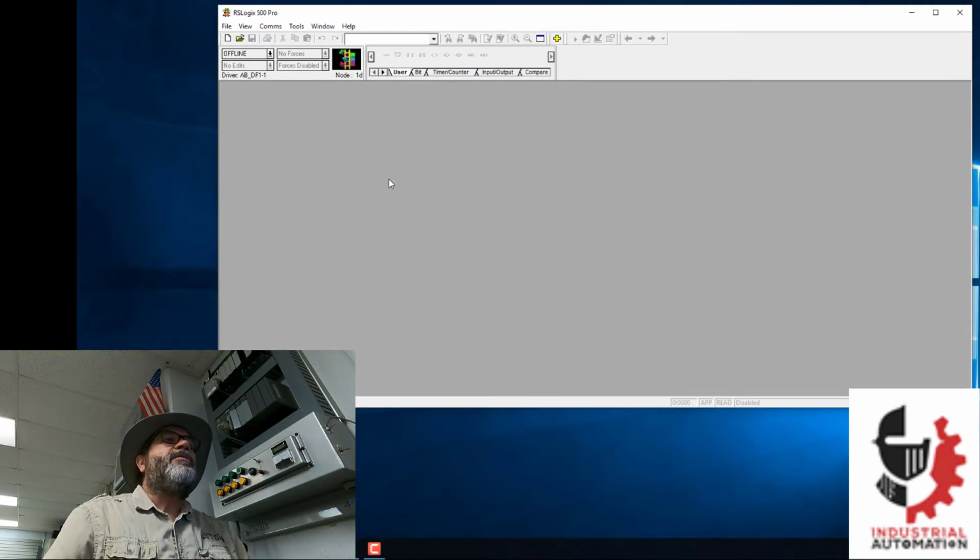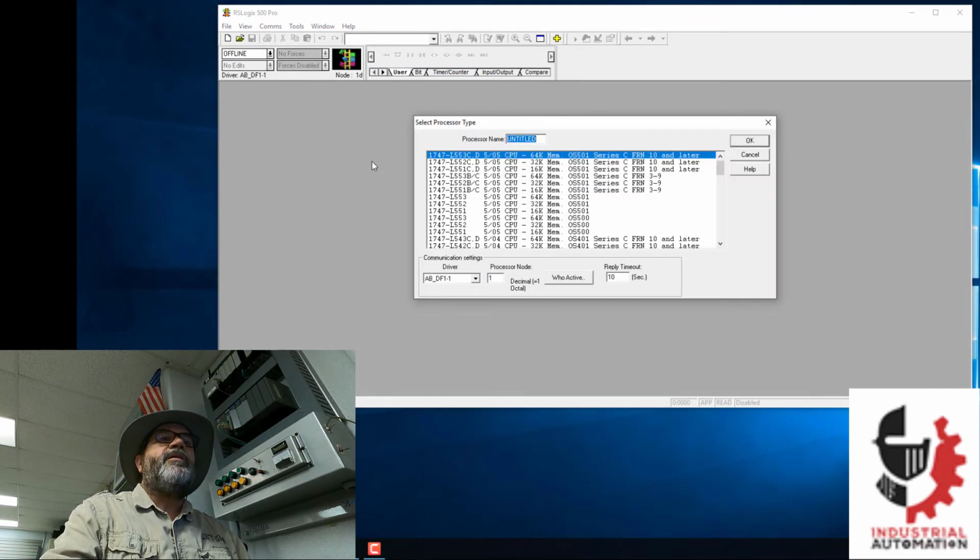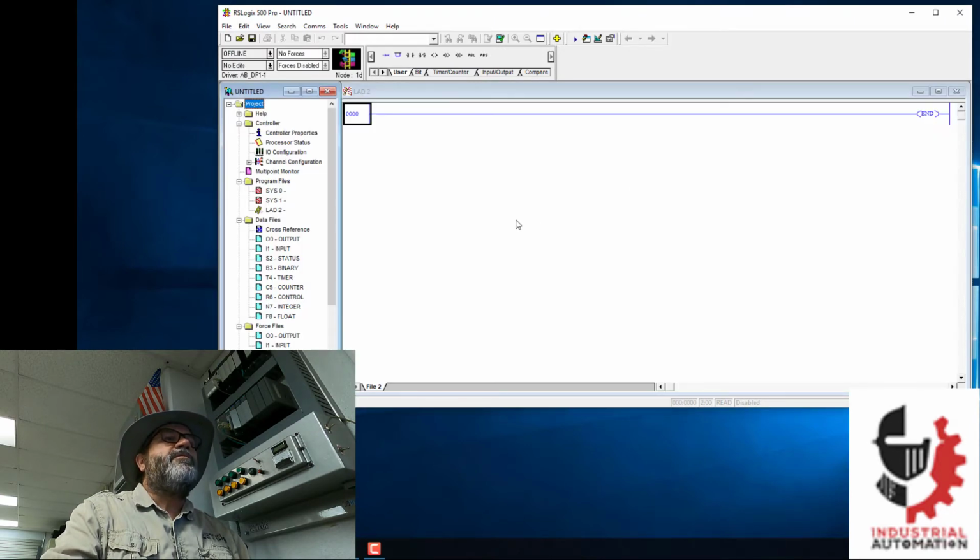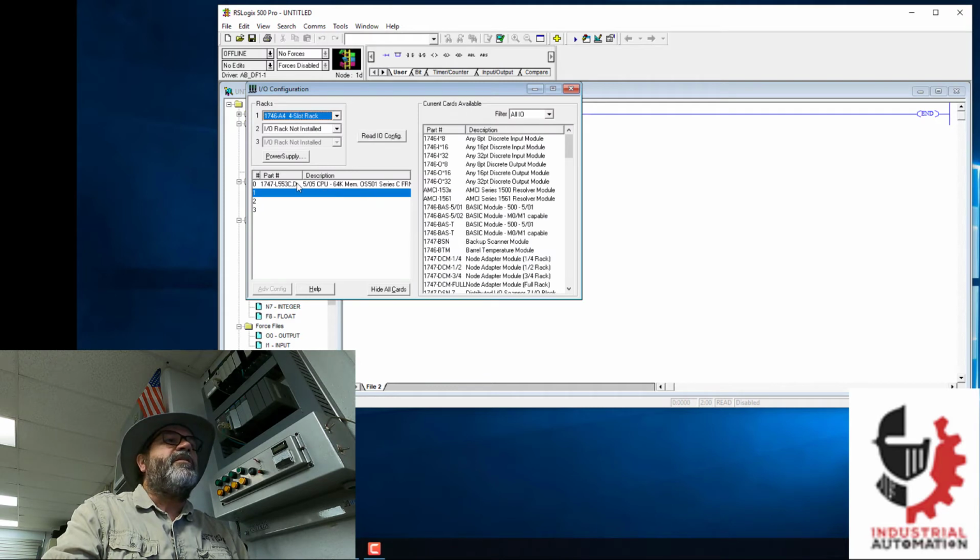Okay, here I've got RSLogix Pro open, and I need to open a new project. So I'll click on New. And I don't care which of these controllers are selected, because I'm going to have the software do the configuration for me. So I'll just leave it at the first one. Hit OK. Alright, I'm going to open my I/O configuration here. And you notice that it's got this first controller I selected, and it's got no information about the slots. So I want to read the I/O configuration. That's right here in the center.